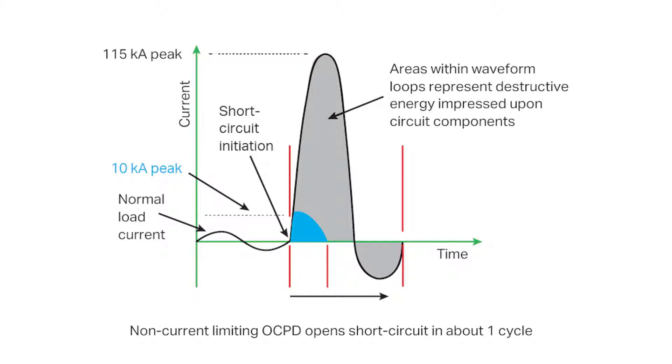The shaded area under the curve represents the energy being dissipated in the circuit, with both magnetic forces and thermal energy being directly proportional to the square of the current, making it important to limit the short circuit current to as small a value as possible. The maximum magnetic forces vary as the square of the peak current, and the thermal energy varies as the square of the RMS current.